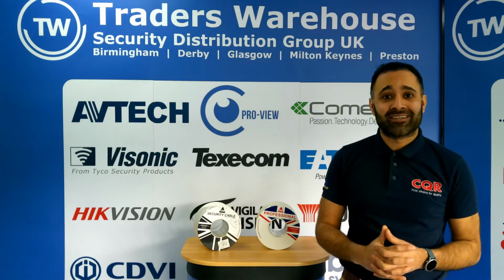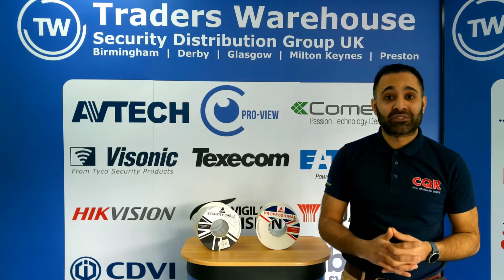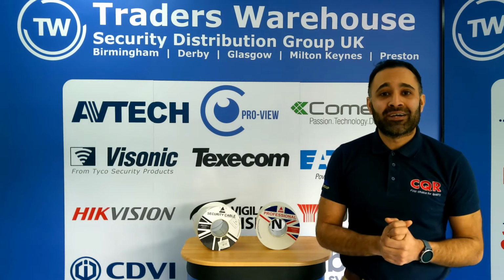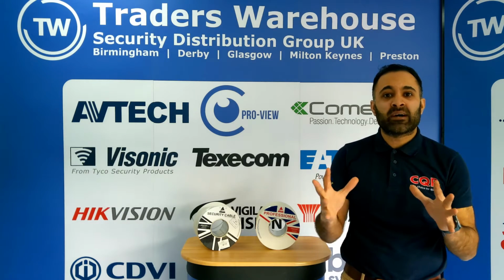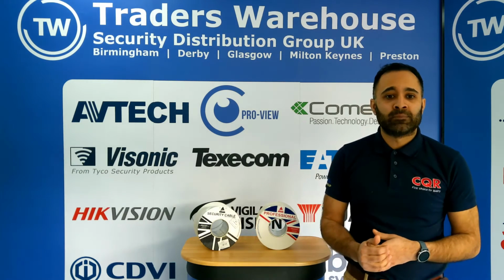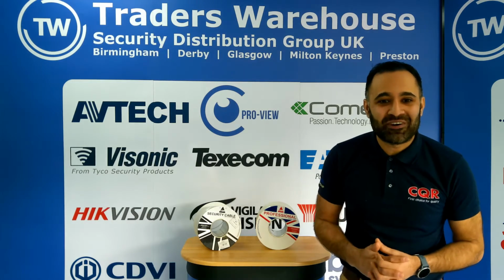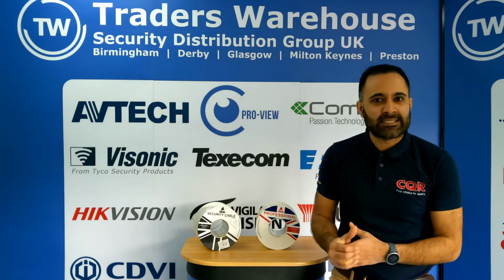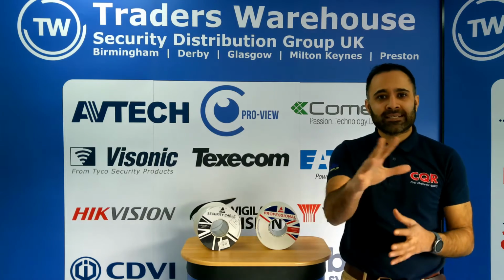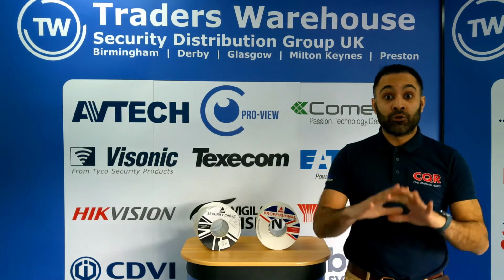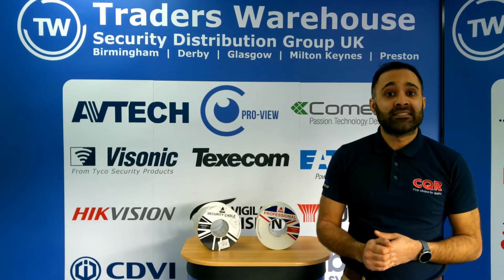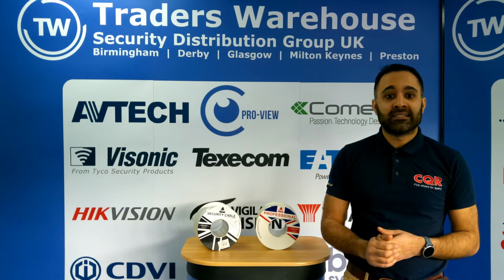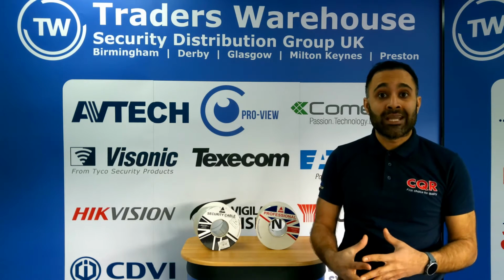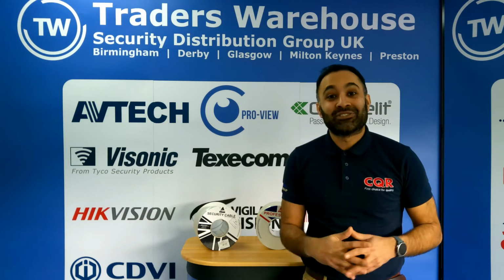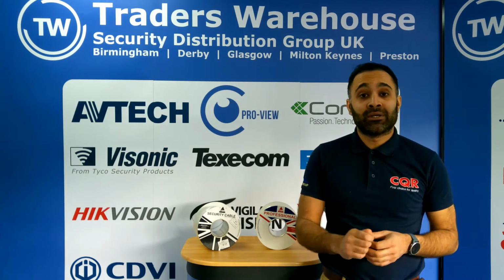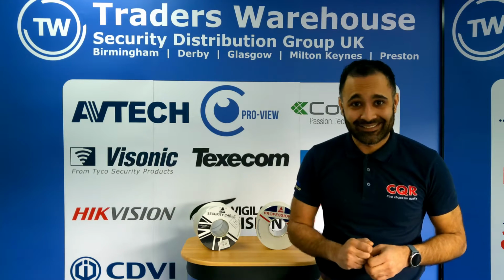My name is Kabir, I'm the Senior Sales Manager of CQR Security, and today I am going to discuss CPR of cables. So that's EN 50575, the 2016 edition. This standard was brought out European-wide in 2017. And it is a regulation, so it needs to be adhered to, and it's your job as an installer to ensure that your cables meet the standard.